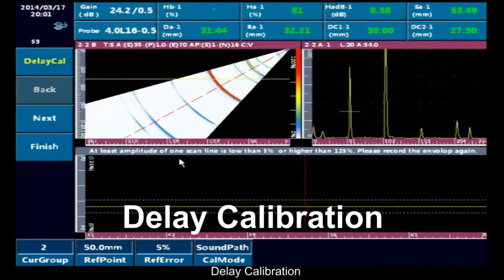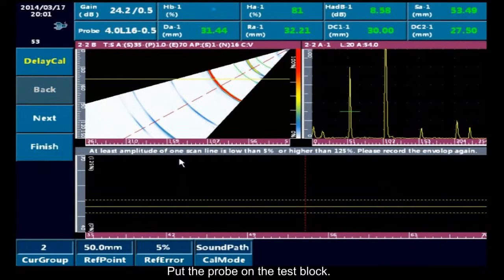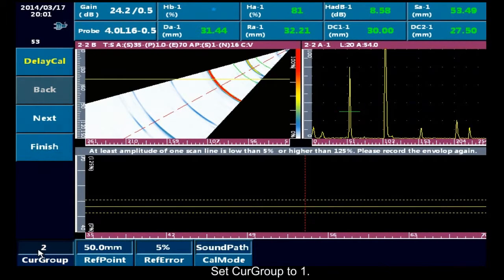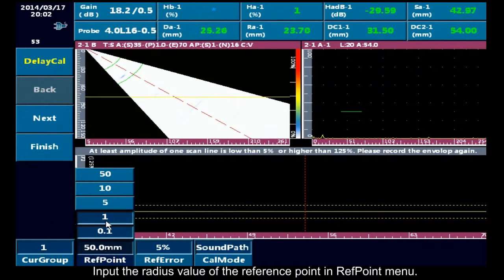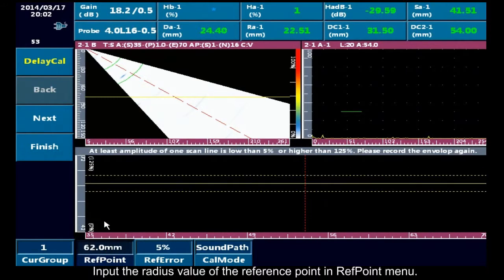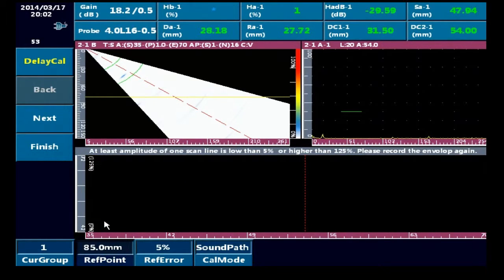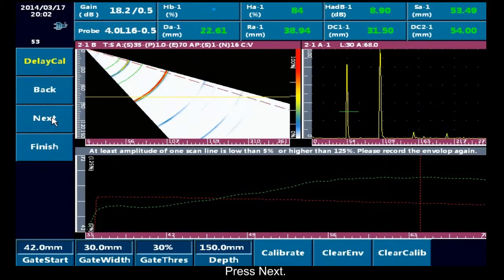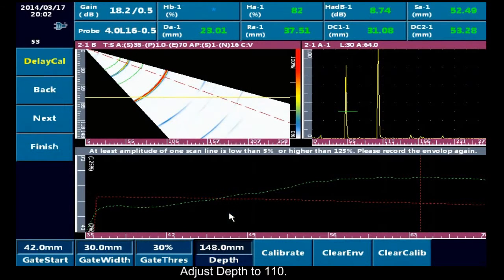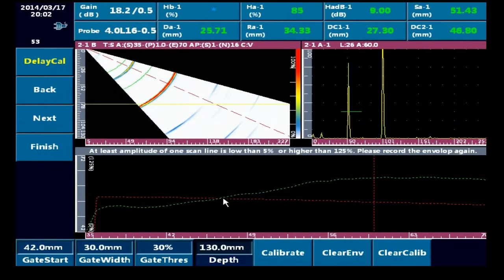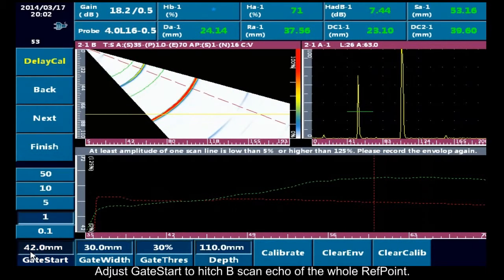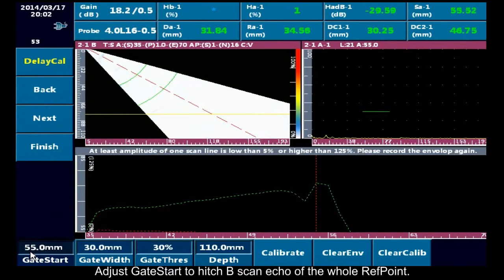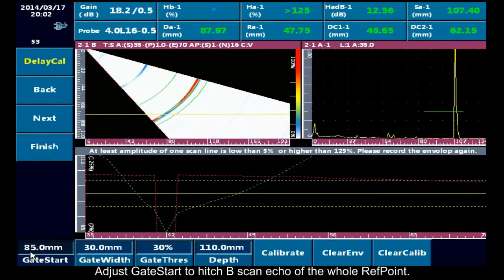Delay calibration. Put the probe on the test block. Set CurGroup to 1. Input the radius value of the reference point in reference point menu. Press next. Adjust Depth to 110. Adjust gate start to hit B scan echo of the whole reference point.